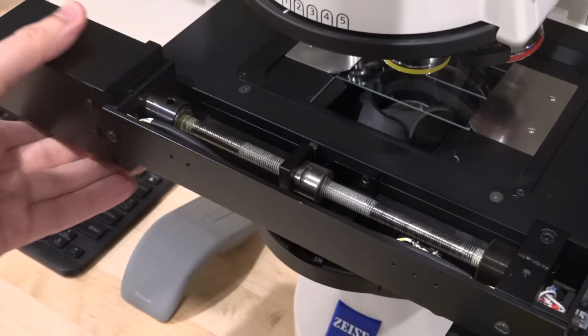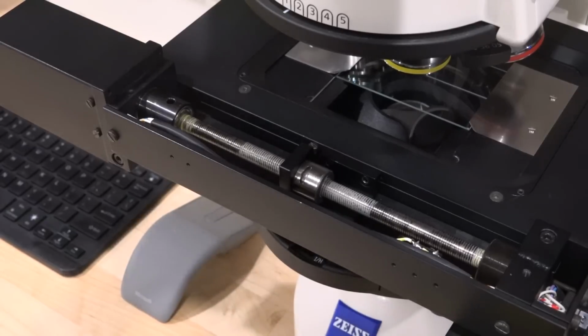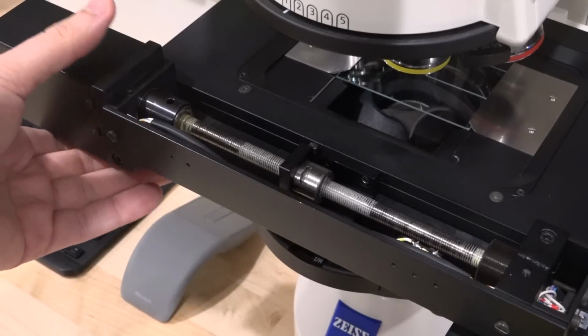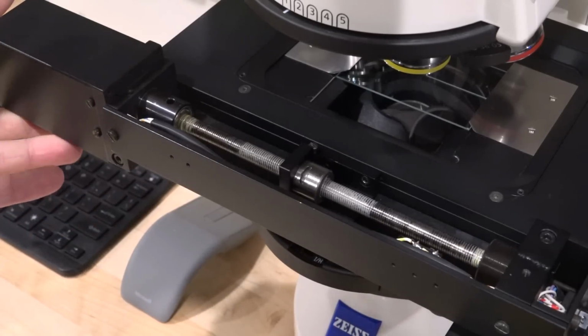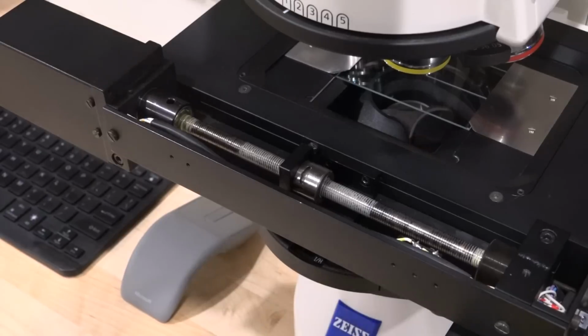There's a DC motor in here and an encoder in the back of it, and a PID controller wrapped around the entire structure inside the controller. That PID controller is always monitoring the precise position of the DC motor using the encoder. So when this thing is energized, I actually can't turn this, because if you turn it, it will resist that movement. There's a PID controller around it, and it will constantly correct it. As a result, the instrument always knows the exact location, no matter what the mechanical pressure is on the system. And this is pretty important for something that needs to move submicron distances, of course. So it's a lot of very precise measurement and, of course, mechanics.